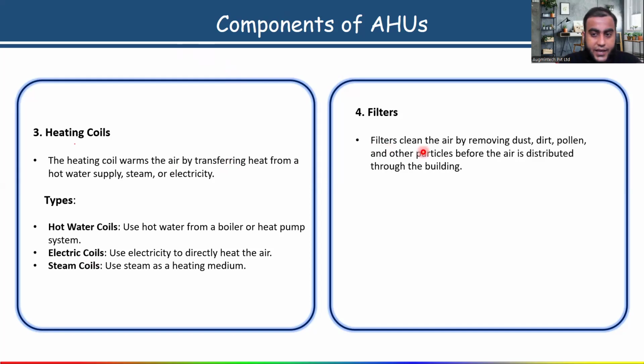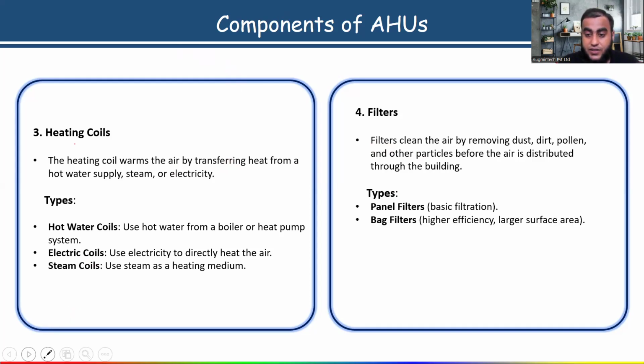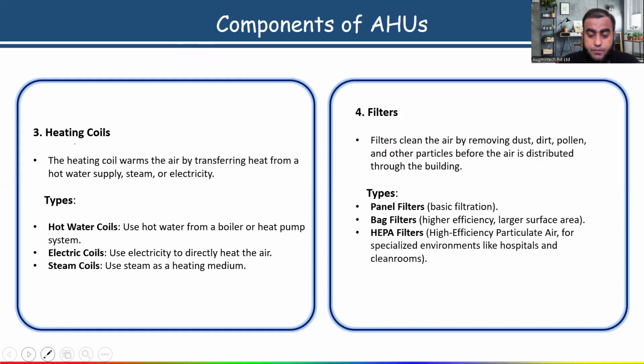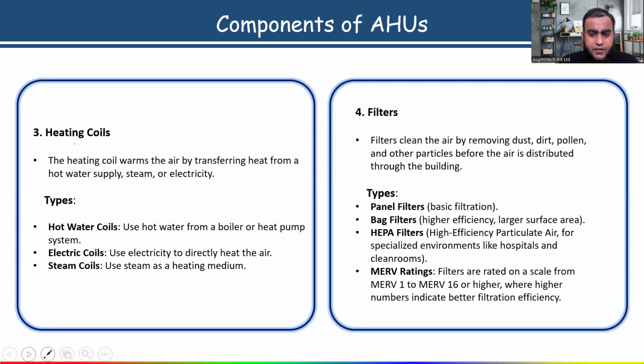Filters clean the air by removing dust, dirt, pollen, and other particles before the air is distributed through the building. Here some types are given, like panel filters, which are our basic filtration, then bag filters. HEPA stands for high efficiency particulate air, used for specialized environments like hospitals and clean room applications. Is it clear? MERV rating filters are rated on a scale from MERV 1 to MERV 16 or higher, where a higher number indicates better filtration efficiency. I will explain all that to you.